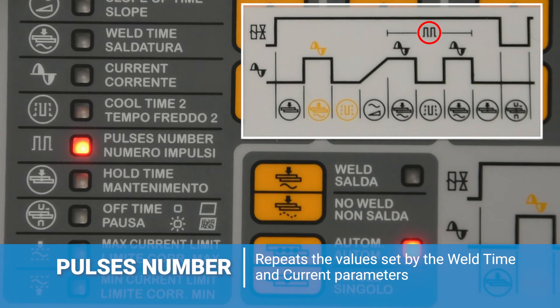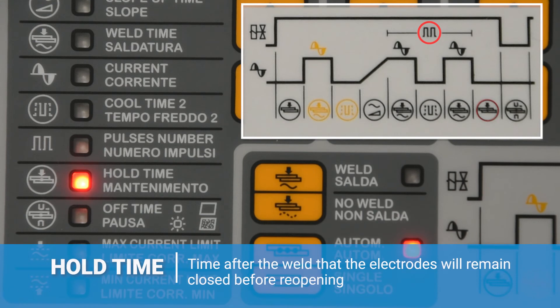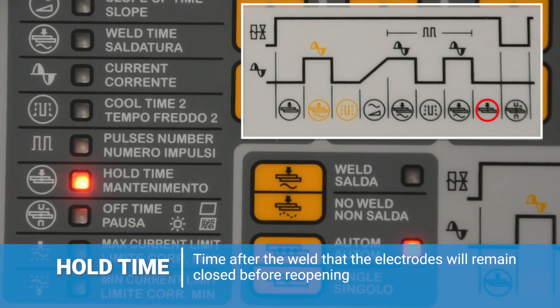A pulse will repeat the value set by the weld time and weld current parameters. Next, we have hold time. The hold time can be set between 0 and 99 cycles. This is the amount of time that the electrodes will remain closed after welding before reopening, and may allow the molten material a chance to solidify.